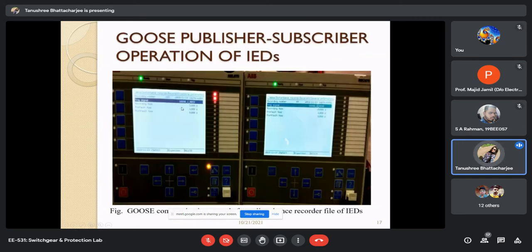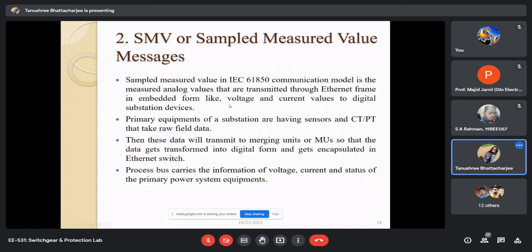For example purpose, GOOSE is a digital signal, and as we mentioned, IEDs can read only digital signals. So we configured the boolean 00011011 into 4 gate signals in one IED, and when we trip manually, that signal transfers from this IED to this IED, and these LEDs turn on. This tells us that GOOSE is traveling well between the IEDs.